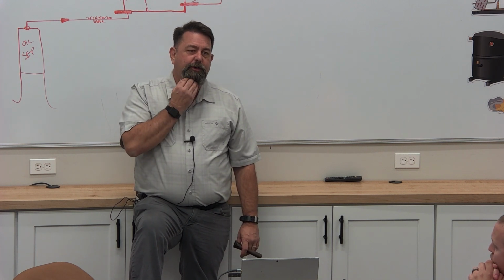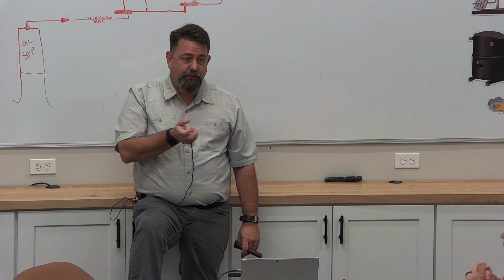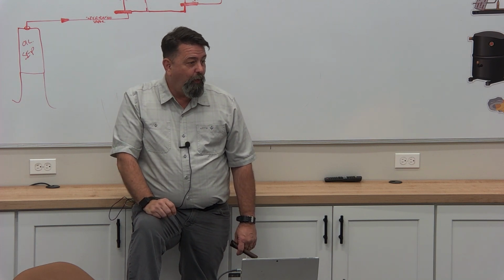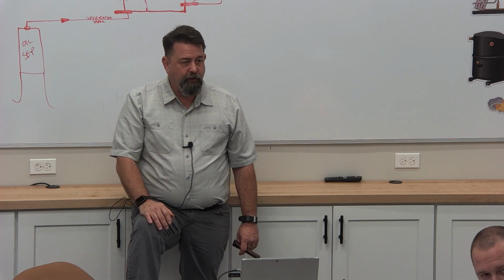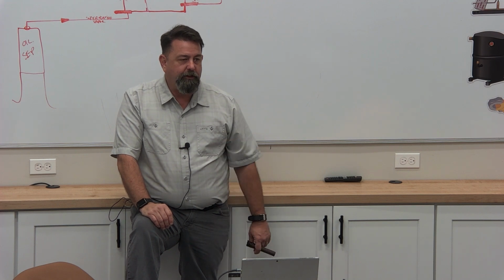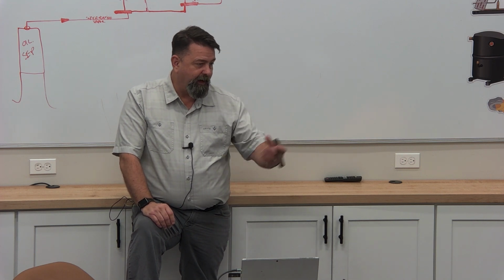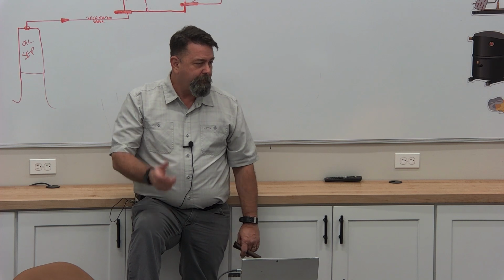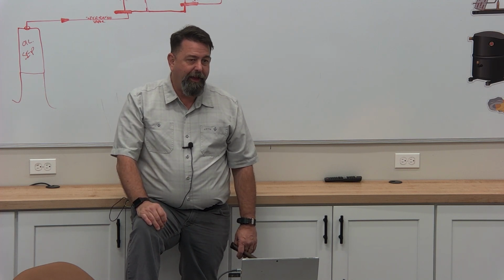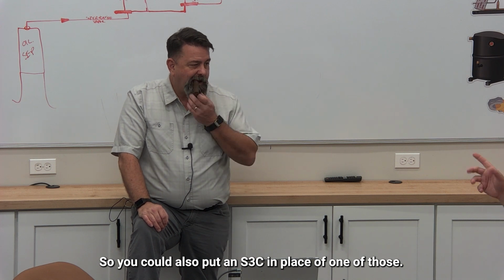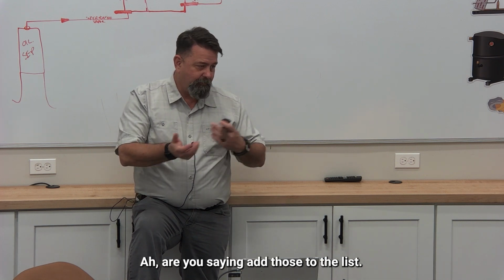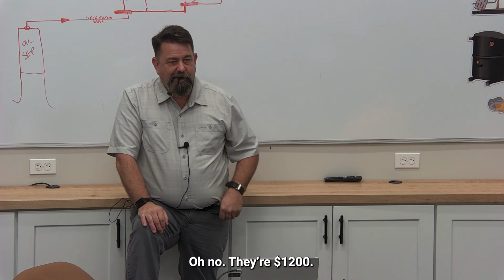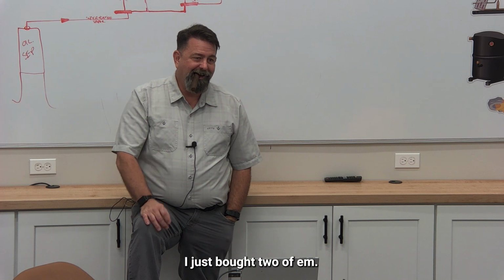So if I had an S3C go out in a case that was controlling an electronic TXV, you could put in one of those and run that case until you got your S3C sorted out. You don't have to leave the case down and out - you can put one of these in and it will drive it. Now, you're gonna land your pressure and temperature, it's gonna calculate superheat, you tell it what its target is, you just program that in. So you could also put an S3C in place of one of those - add them to the list, even though they're $1,200 difference, but they will work. I just bought two.